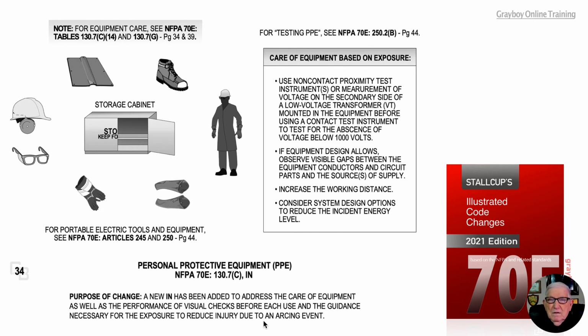Now, we know that for testing PPE, we would see 70E 250.2b on page 44. For equipment care, in accordance with the note to the left top side of the illustration, we would see 70E tables 130.7C 14 as well as 130.7G, basically on pages 34 and 39.